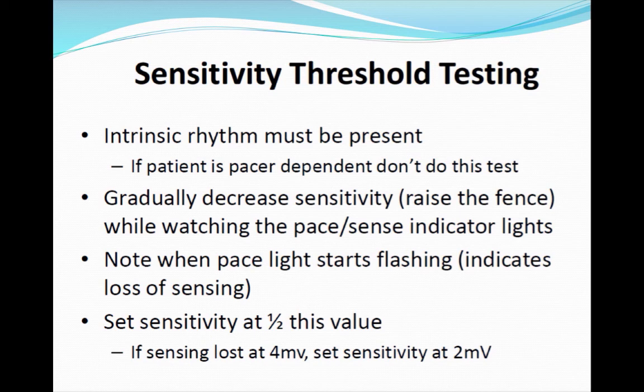These are the steps for testing the sensitivity threshold. The patient must have an intrinsic rhythm, then gradually decrease the sensitivity — raise the fence — while watching the pace and sense indicator lights on top of the pacer. Note when the pacing lights start to flash, indicating loss of sensing. The sensitivity is then set at half of that value; so if sensing was lost at 4 millivolts, set the sensitivity at 2 millivolts.